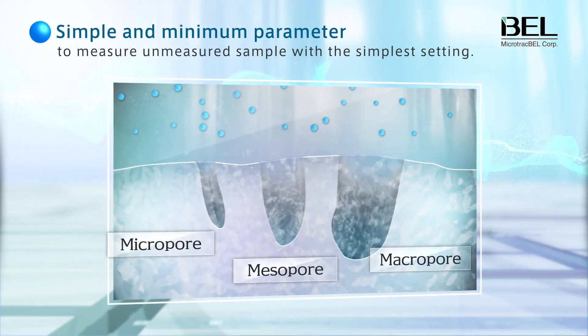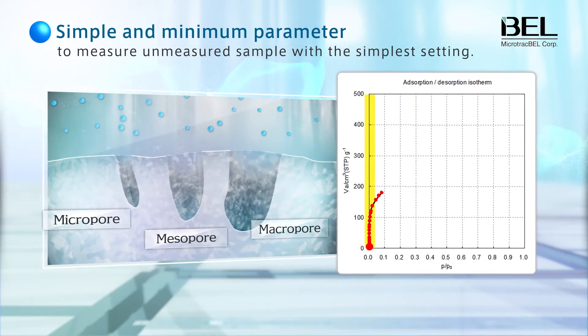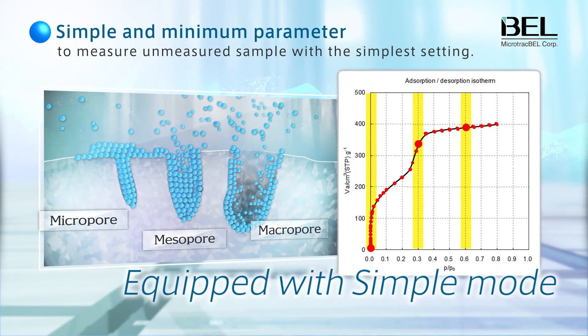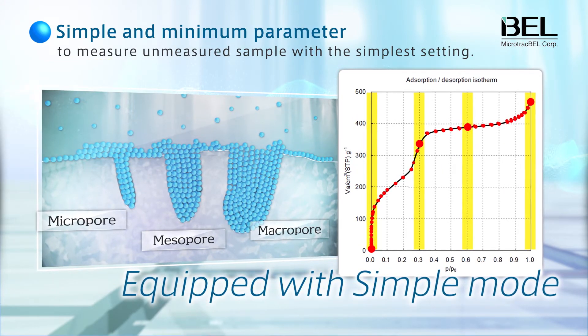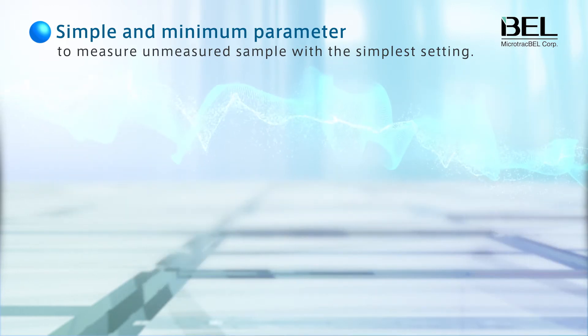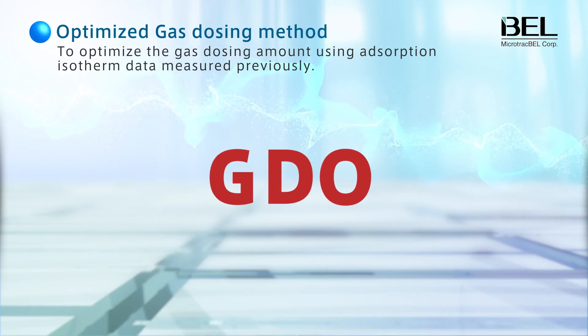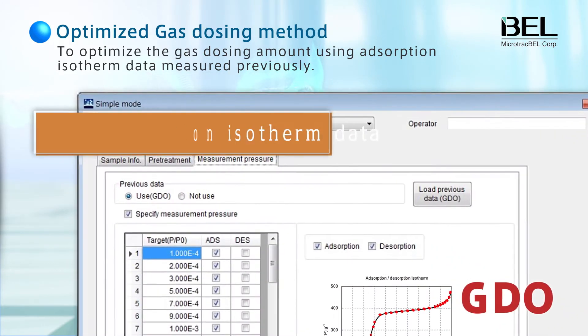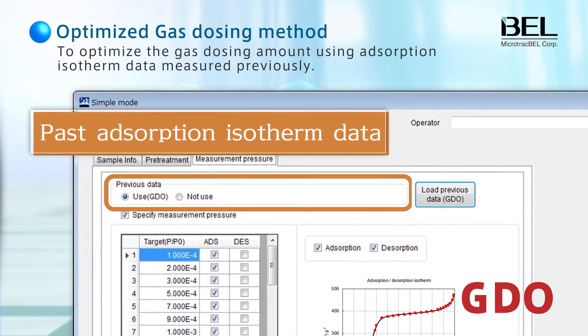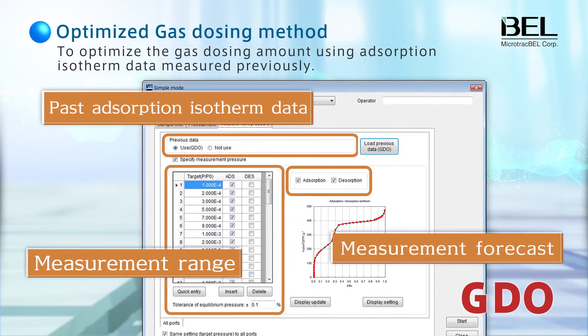The simple mode is useful for unmeasured samples with minimal setting conditions. The Gas Dosing Optimization, or GDO, automatically calculates gas dosing conditions using relative pressure and adsorption data from past isotherm data.